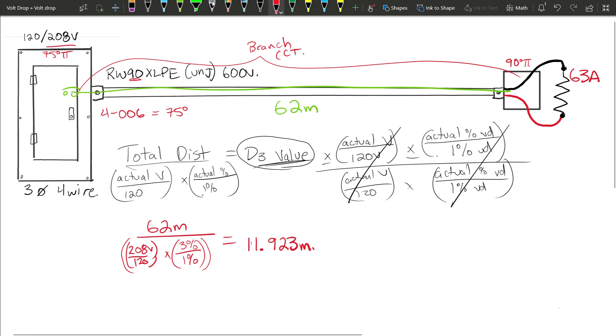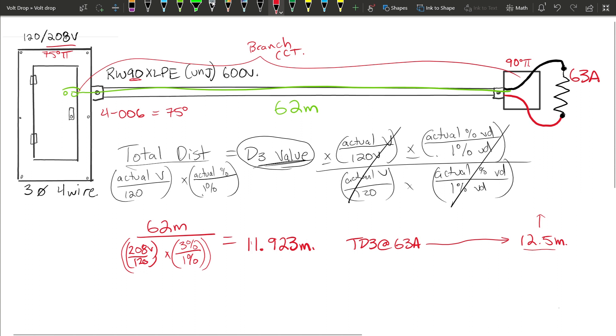Based on the D3 values, we're looking for a number around 11.923 meters. We know we're using a 63 amp load, so going to Table D3 at 63 amps and reading across, we find 9.9 meters — which is too small — and 12.5 meters. Looking at where 12.5 meters lands in D3 and going straight up to the conductor size listed, that gives us a Number 3.